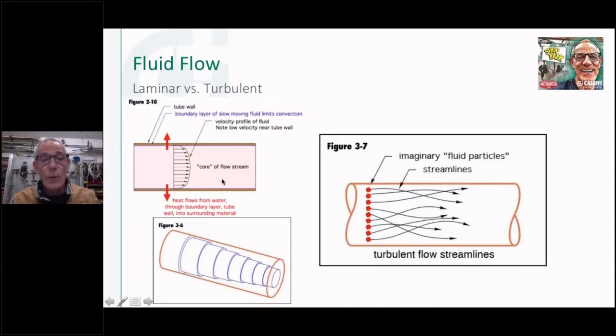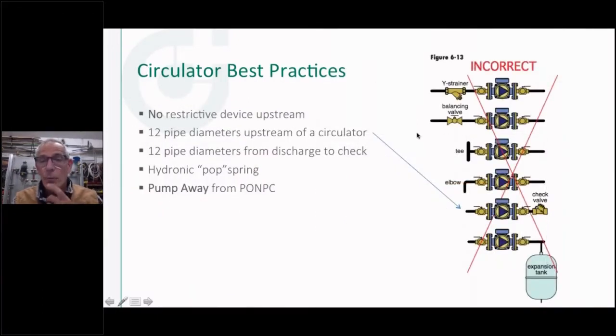So we can predict when this happens in a tube if we know the size of the tube and we know a couple of pieces of information, and I'll show you how we do that. But one of the questions that came up, and I'll go back a slide here, when using the old style air purgers, the scoop or the ramp type air purgers, I heard somebody say, well, you want that 18 or 24 inches upstream of that so the flow can go laminar. Well, that's not exactly what happens there. The only way the flow can go laminar is if you slow it way down, way down, below a foot per second velocity.